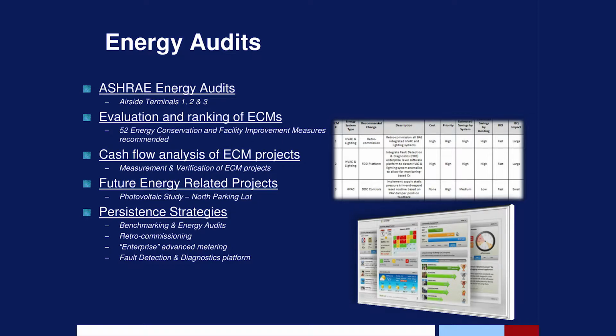Now, we started with an ASHRAE Level 1 because it makes sense, when tackling something this large, to use a triaged approach. You don't want to throw a Level 2 or Level 3 effort at something this massive until you've scaled down and zeroed in on exactly which energy conservation measures you really want to invest time and effort into understanding more. A lot of this is low-hanging fruit tied up in the controls environment, so it doesn't really need that extra level of analysis.